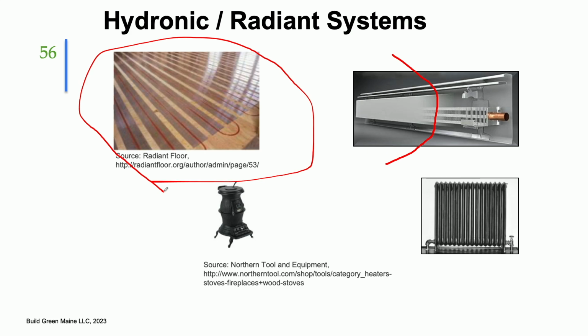One option: they do make air-to-water heat pump systems that will feed into a radiant floor system. So you can do that with a heat pump instead of using a boiler. It's definitely possible, it's fairly new technology to the state of Maine. I've seen houses that are heated that way. It works, it's not cheap. Most heat pump installers have never seen that equipment yet, so it's going to be hard to find somebody, but it does exist. Forced hot water baseboard, it is really, really hard to do that with a heat pump. So radiant you can do.